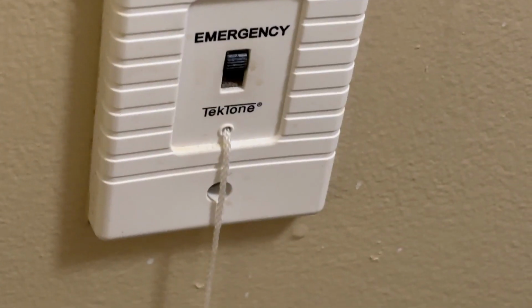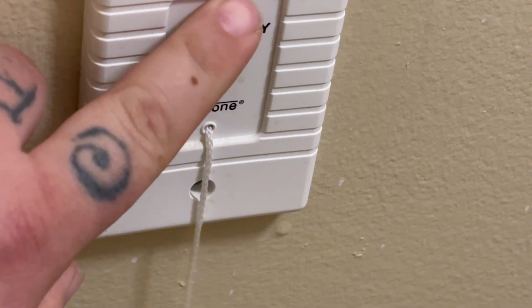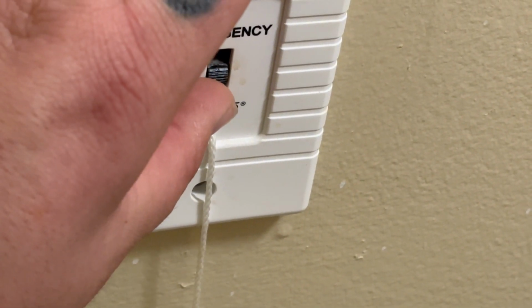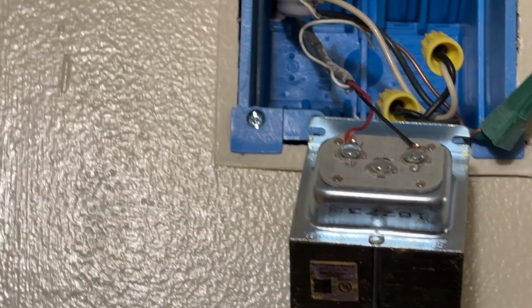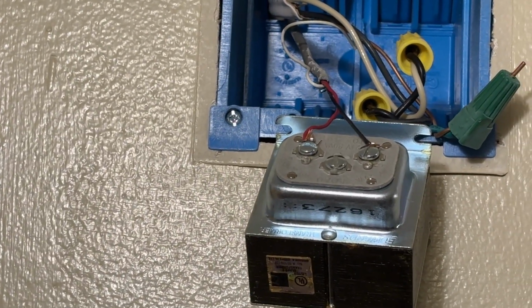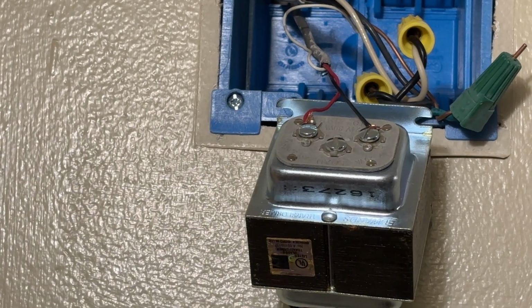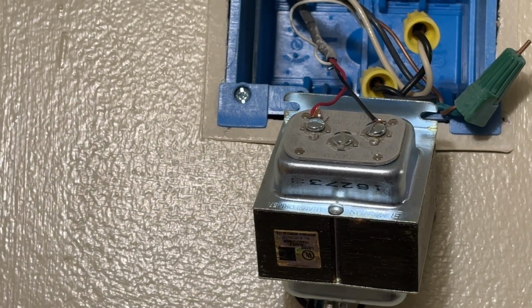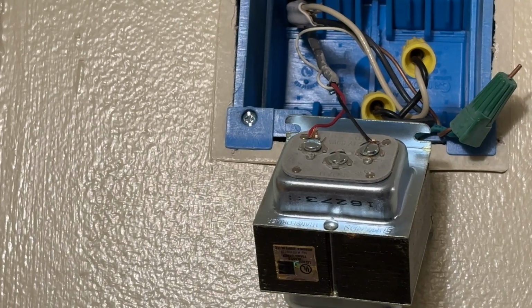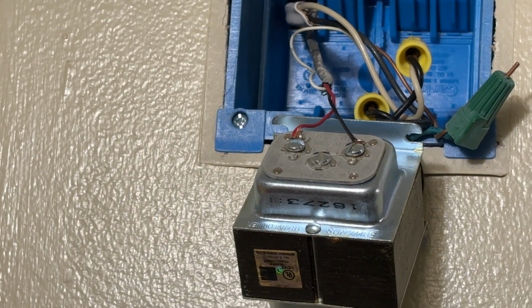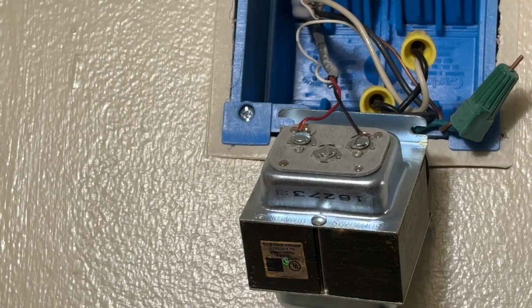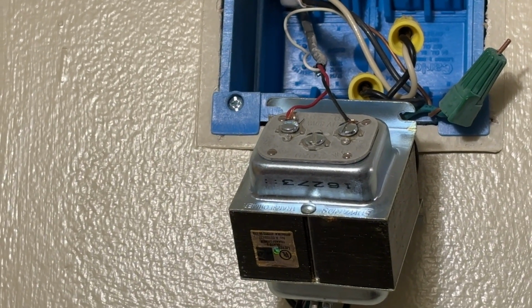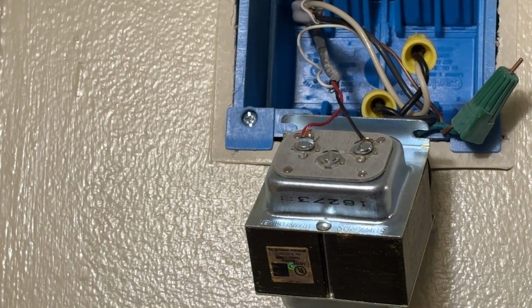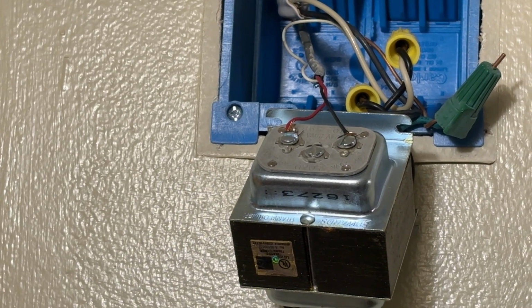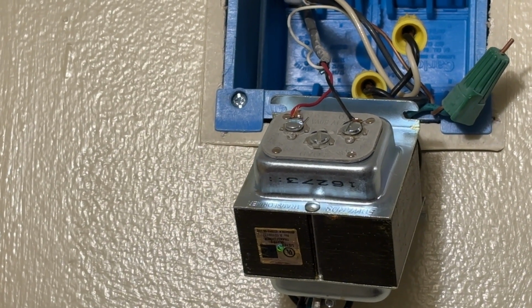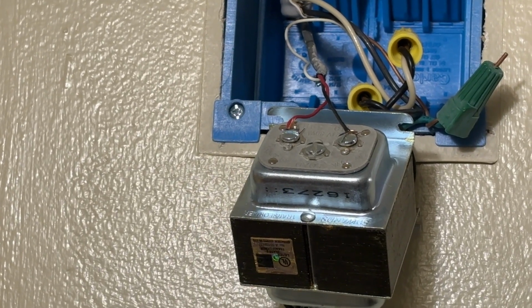We would activate our pull cord by pulling the string or flipping the switch. And with our pull cord activated, we would test the voltage between our two low voltage wires, these red and black, again, and see if our voltage drops. If the voltage drops, we know we're sending a load out, so our switch is working and it is calling for that siren to activate. So with our voltage dropped, we will go and remove the siren from the ceiling outside.